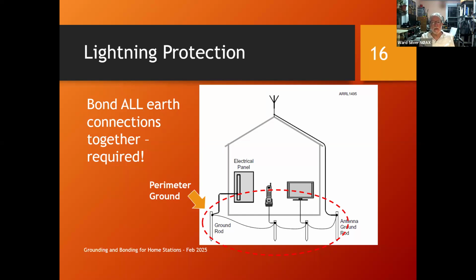And so what do you get between those two ground terminals if you say you had a 1,000 amp lightning surge through the earth? That's no big deal. That's not even a really large lightning surge. If you have 1,000 amps flowing through, say, 10 ohms, you've got 10,000 volts between this point and this point, just because these things are only connected together with dirt. The conductivity of dirt is not very good. So that's why you replace it with a bonded wire.